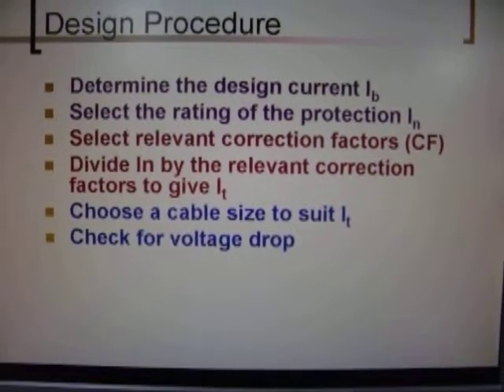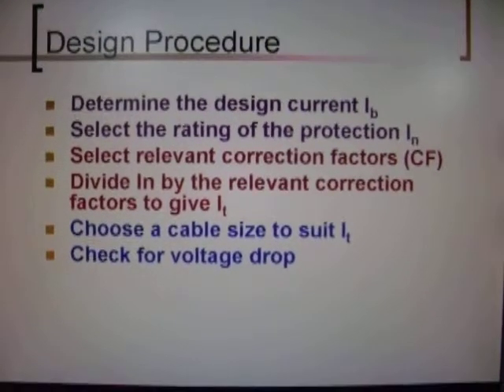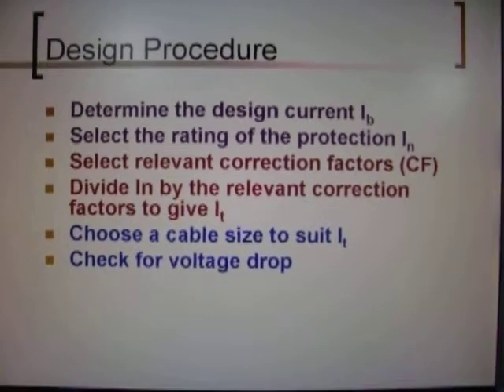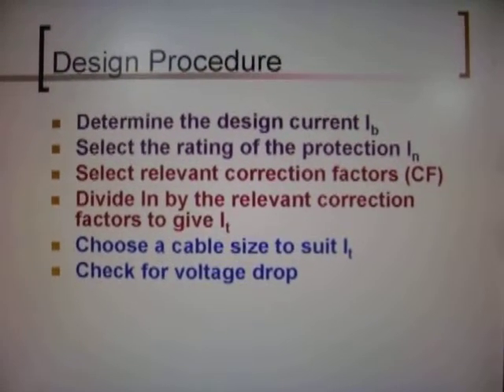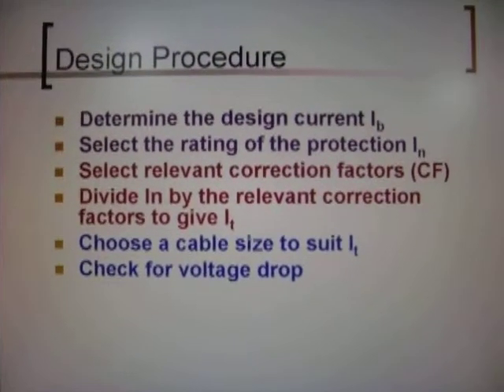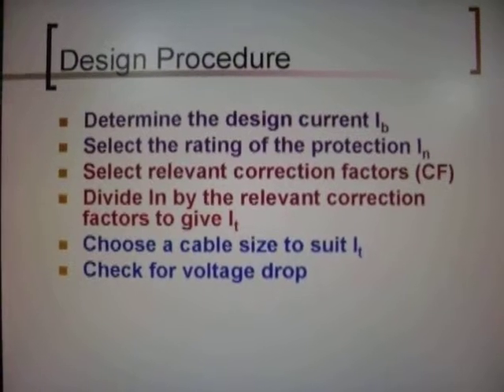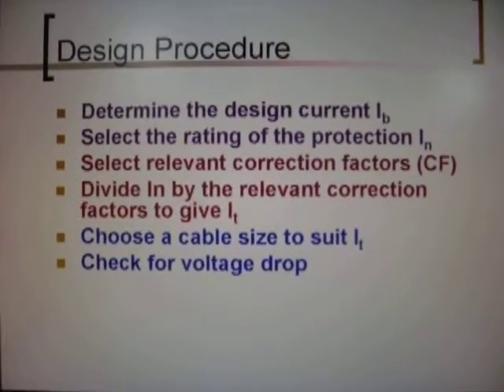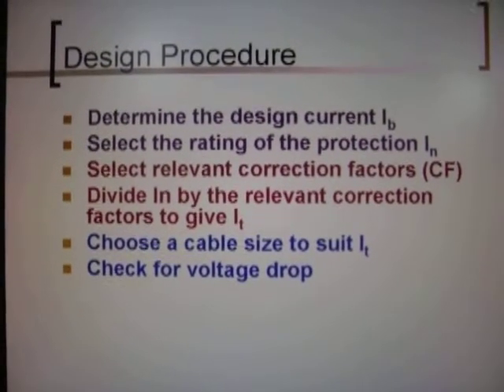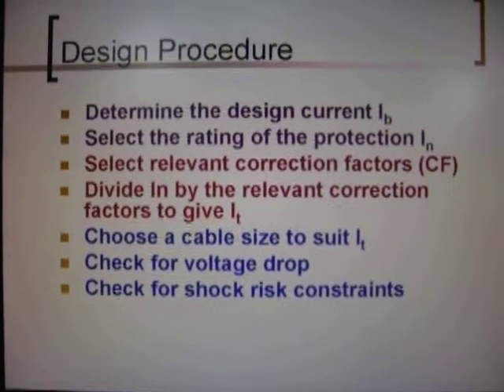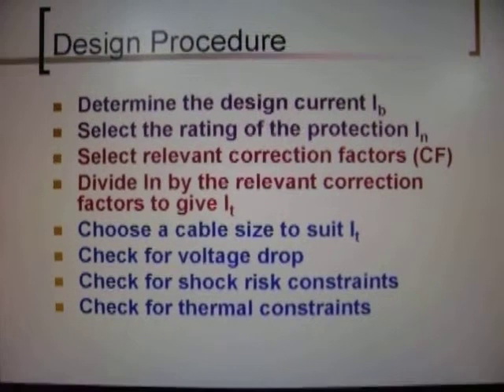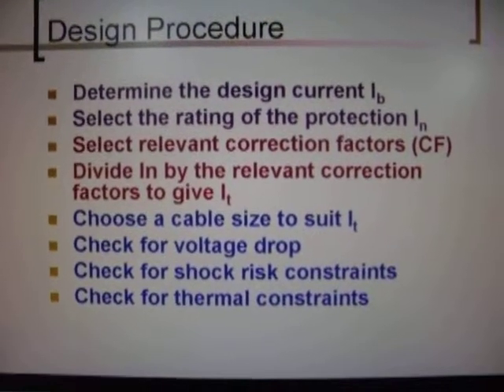Choose a cable size to suit IT and check for voltage drop. Remember that in regards to designing your cable to carry your current, the cable must be able to handle the current it's carrying at a given point. So there are certain factors which determine the actual size of the cable to carry that given current. If your cable is carrying 5 amps or 30 amps, there will be an applicable factor. Check for shock risk and thermal constraints.